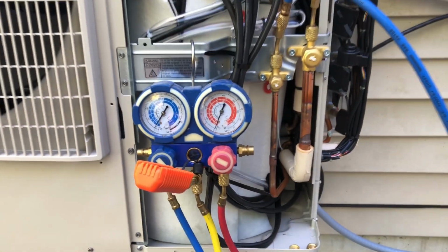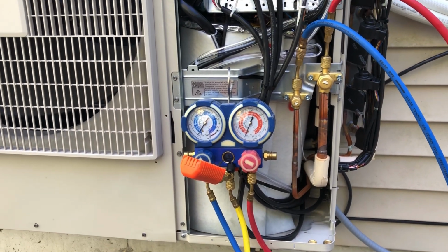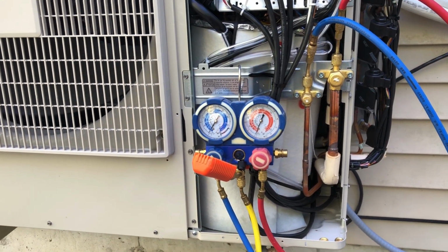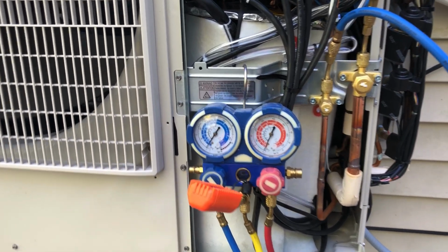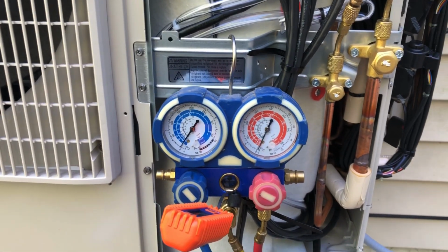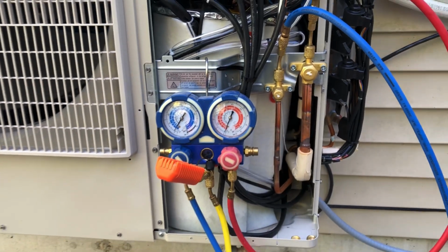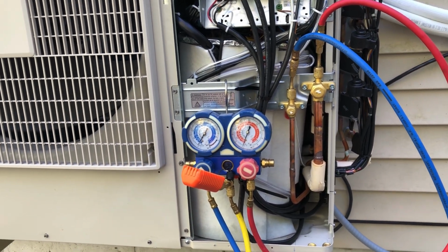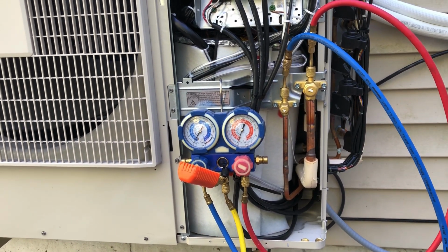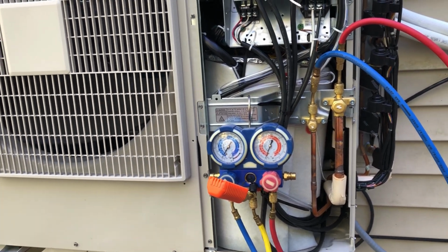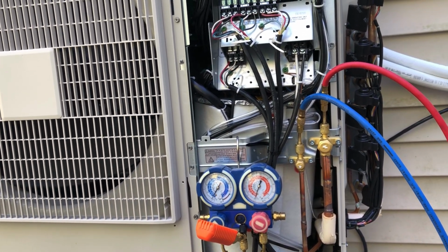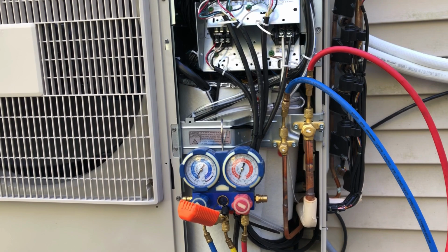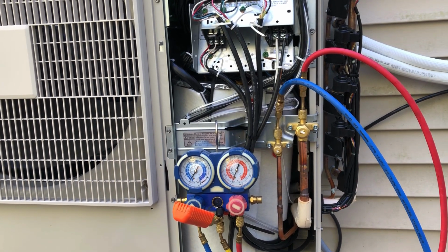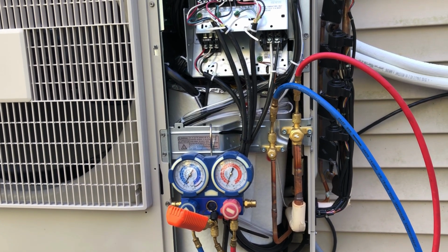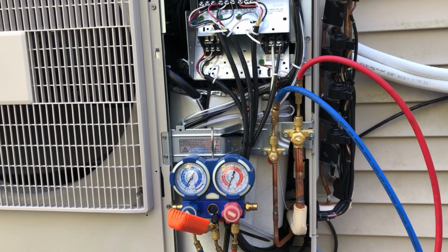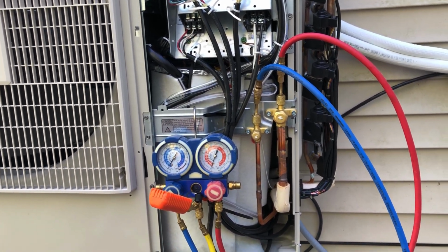It usually takes about 15-20 seconds for the gauges to stabilize, then you just sit and wait to see if it drops at all. If it drops, you've got a leak somewhere, so get your soap bubbles out and spray all your fittings to find the leak. So that's what I'm going to do now - hit about 500 psi and leave it for a couple of hours to see if there's any drop.